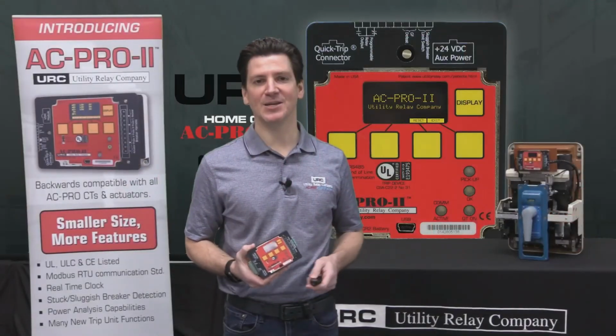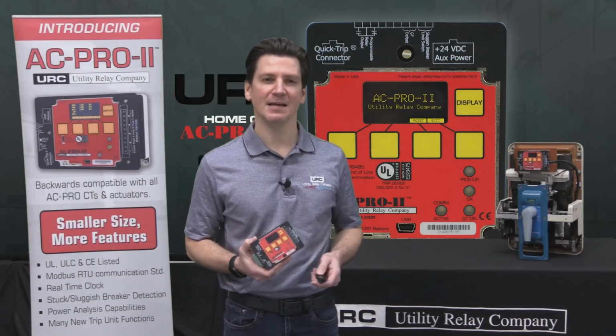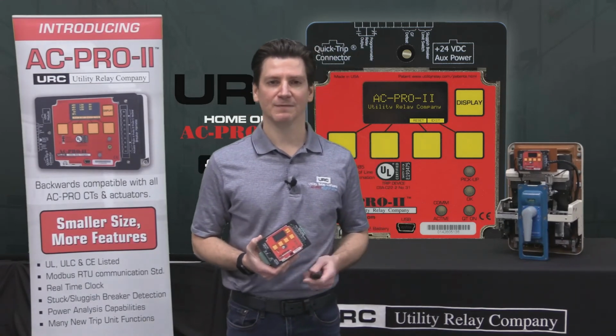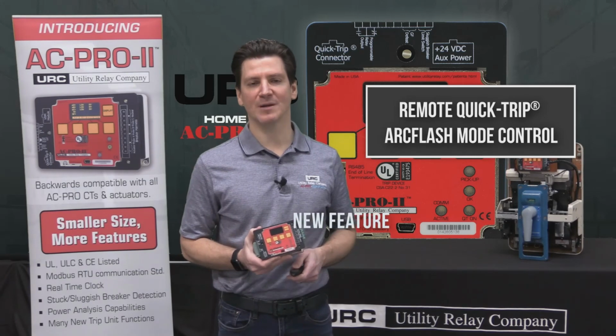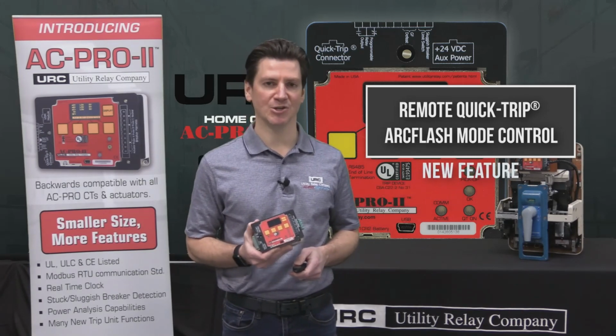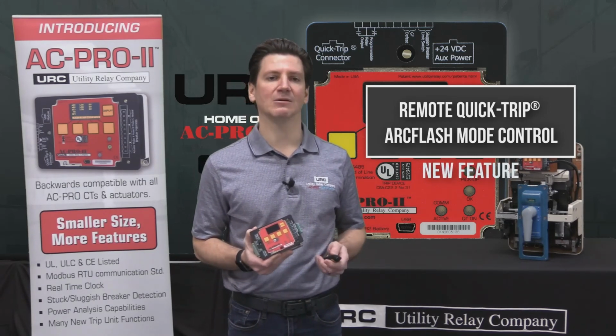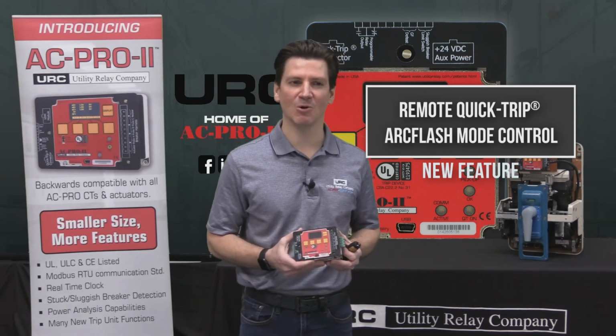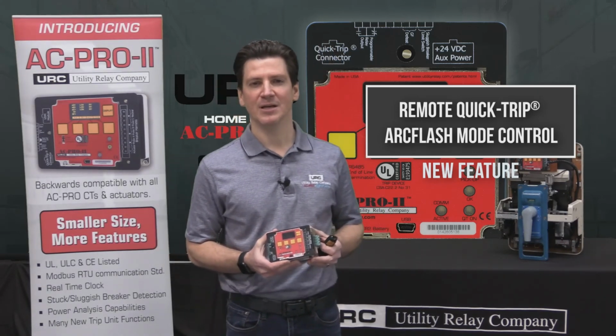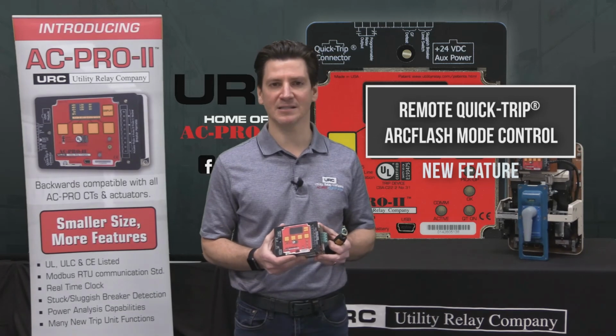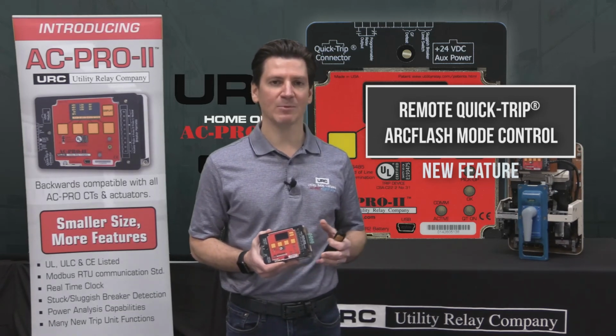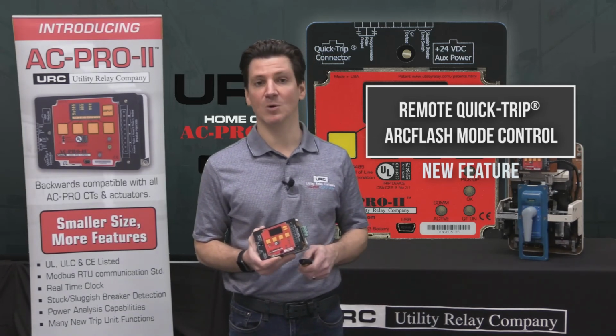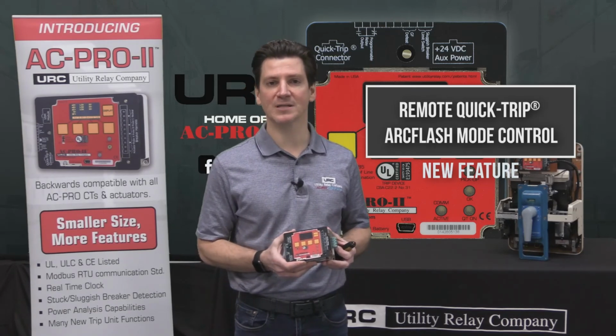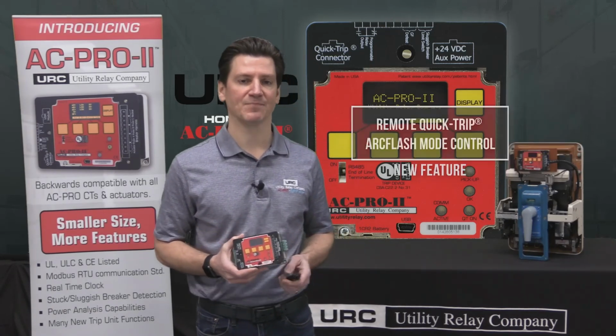There are actually 10 new features with this update, but today I'm just going to highlight 3 of them. Firstly, remote quick trip arc flash reduction mode control. As a reminder, quick trip is a manually controlled arc flash reduction system using separate ground fault and instantaneous settings. Being able to engage and disengage remotely further reduces risk and increases your productivity.